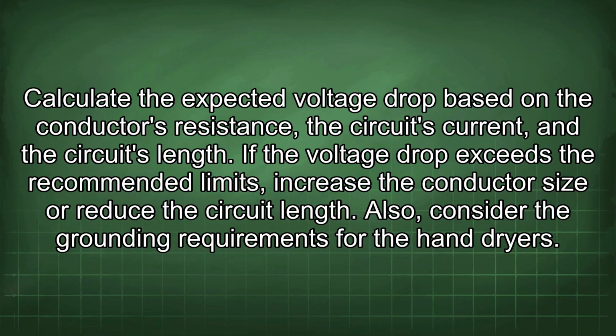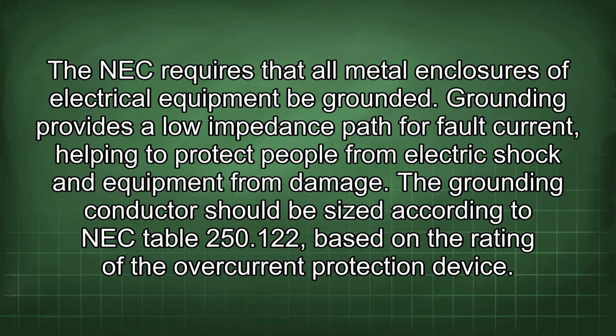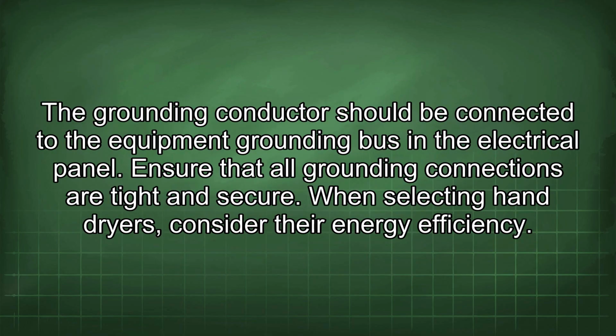Also, consider the grounding requirements for the hand dryers. The NEC requires that all metal enclosures of electrical equipment be grounded. Grounding provides a low impedance path for fault current, helping to protect people from electric shock and equipment from damage. The grounding conductor should be sized according to NEC Table 250.122, based on the rating of the overcurrent protection device. The grounding conductor should be connected to the equipment grounding bus in the electrical panel. Ensure that all grounding connections are tight and secure.